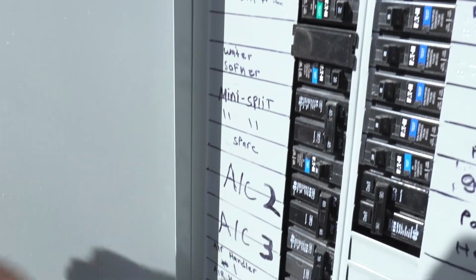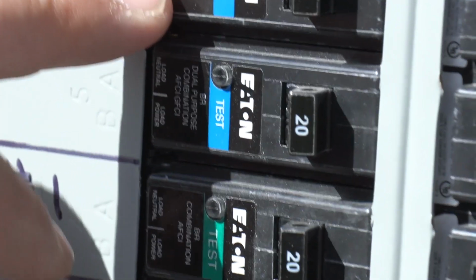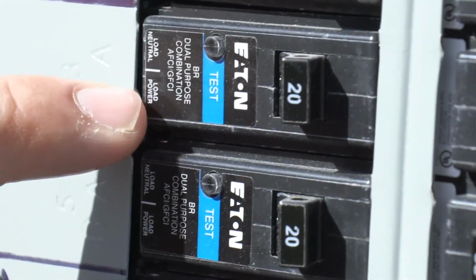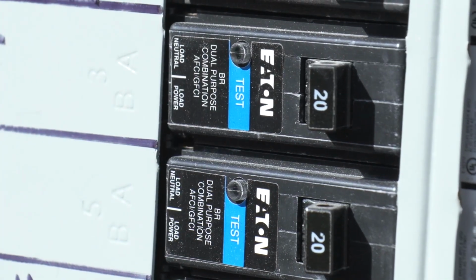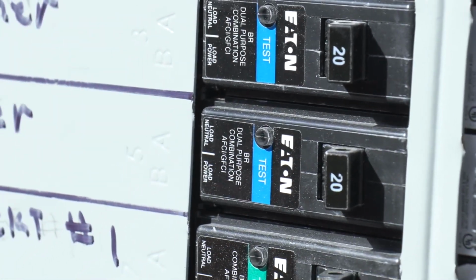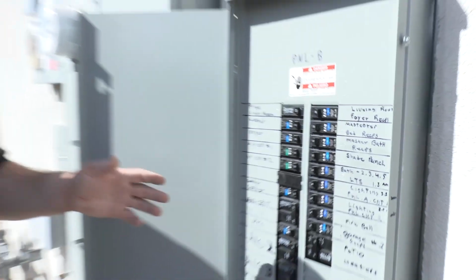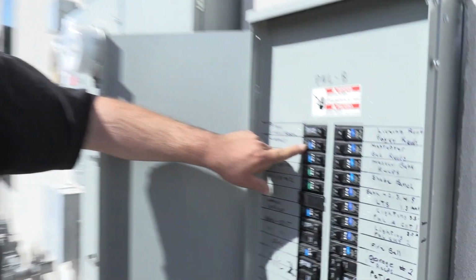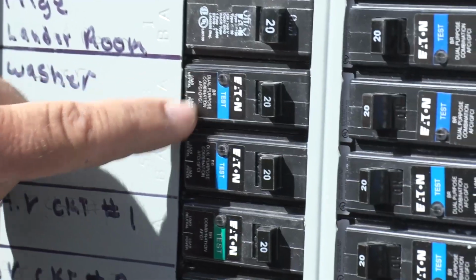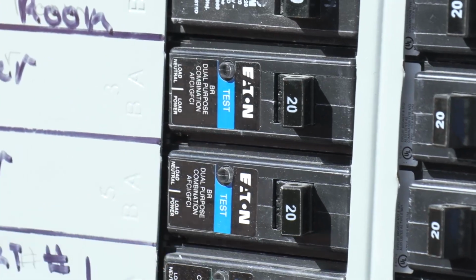Our 2 poles are more advanced. These blue ones are arc fault and GFCI combo breakers. GFCI you might be familiar with. The outlets in your house that have a test and reset button are GFCI outlets. It's a ground fault circuit interrupter. With these breakers, we don't put those outlets in. That function is handled at the circuit breaker. So if it gets wet, or if you get an arc, it'll trip this. You can come out here and reset the breaker, instead of trying to find where that one outlet is that you have to put the reset button on.